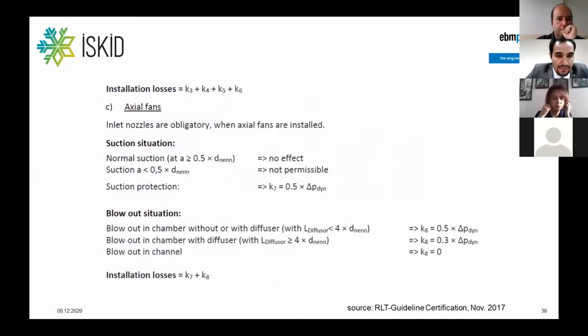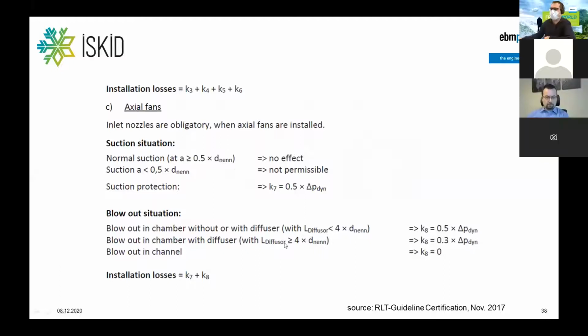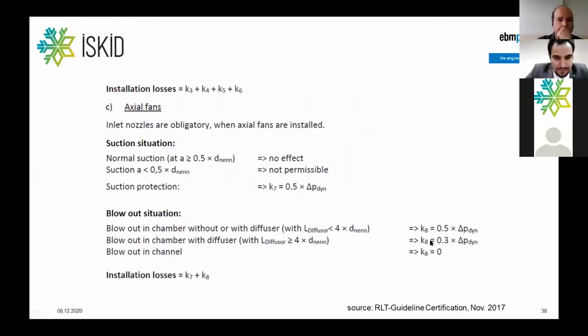And this is also done for axial fans. On the flow side dimension, if there's a diffuser, you have a certain loss to be considered. And especially in axial fans, the dynamic pressure is quite high, as the flow velocity at the outlet of the axial fan is high. So you see here the factor could have quite a high effect on the performance of the fan. That has to be considered.